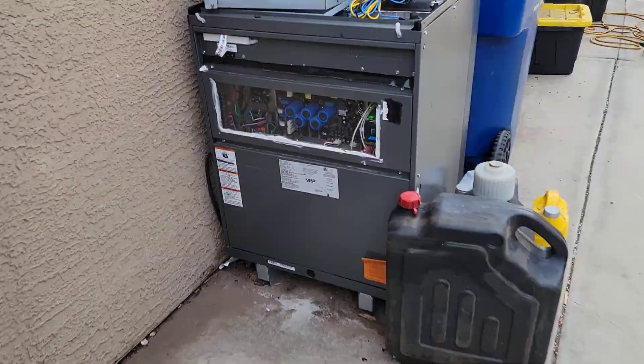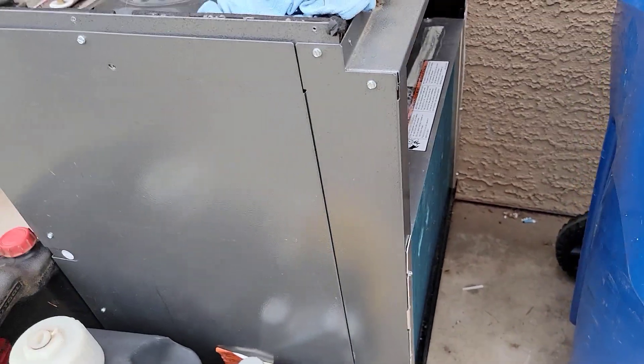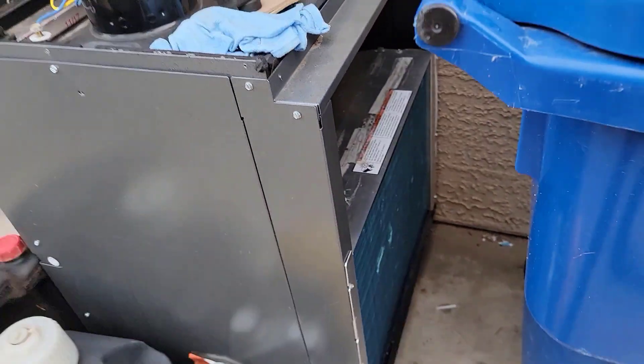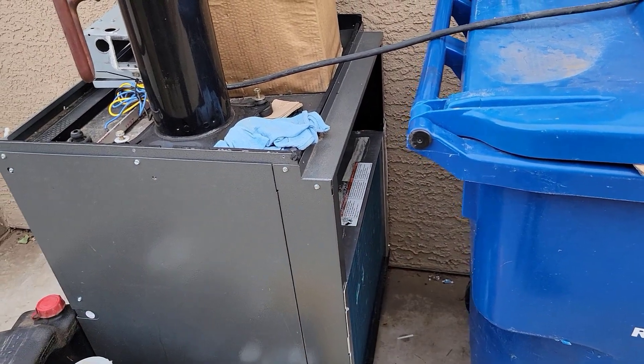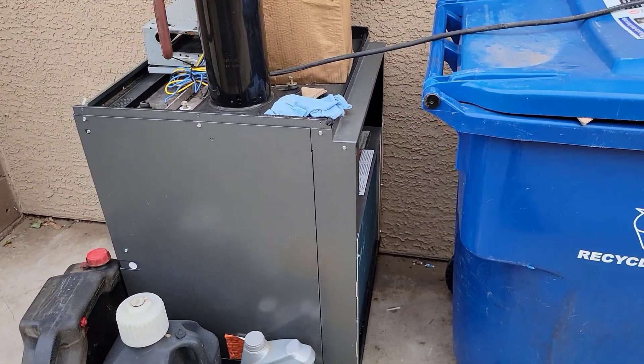You can hear what it sounds like outside — sounds good. My little cardboard temporary splitter got all ruined so I threw it away. I can feel cold air being sucked back in, so it's recirculating cold air — just like in summer it recirculates hot air. It really needs the grill with the divider on it. If I just add a couple inches of a splitter out there it seems to be okay. I just need to cut a piece of sheet metal.